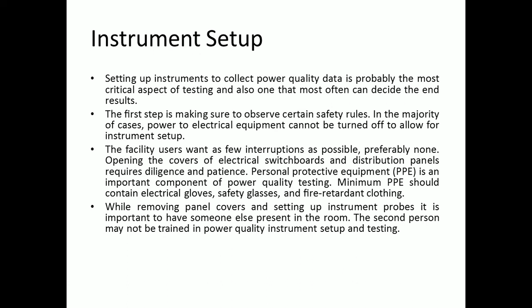While removing panel covers and setting up instrument probes, it is important to have someone else present in the room. The second person may not be trained in power quality instrument setup and testing. Further, installing power quality instruments and probes requires special care. It is preferred that voltage and current probe leads do not run in close proximity to high current cables or bus, especially if they are subjected to large current inrush.